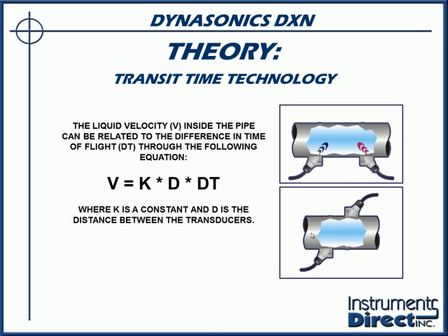Now, we can mount this on the pipe in different configurations. The picture in the lower right-hand corner is the exact example of the man in the rowboat. We usually use this in larger pipe size applications. This is referred to as the Z or the single path method. The upper right-hand corner, the V configuration, is actually what you'll see in the field most often because it's what we use in smaller pipe applications just because it's easier to do. Traditionally, you'll see this in applications in, say, 1/2 to 24 inches. And in this case, we're sending a sound beam across the pipe, reflecting on one side, and it comes down to the sensor on the other side, and we repeat that effort.